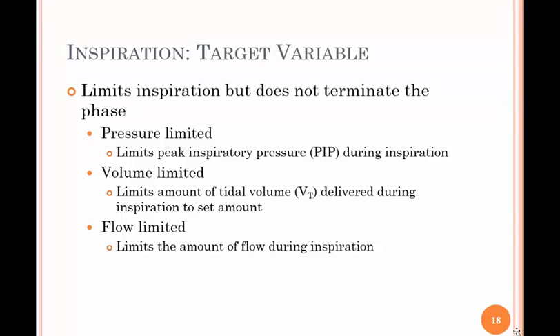The target variable limits inspiration but does not terminate the phase. If you have a pressure-limited breath, this limits the peak pressure during inspiration. Volume-limited limits the amount of tidal volume delivered during inspiration to a set amount. Flow-limited limits the amount of flow during inspiration.